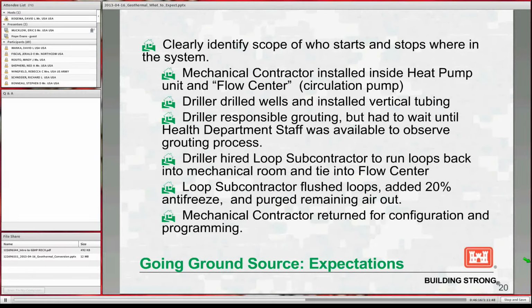The loop subcontractor also has this cart thing that they hook up and flush the tubing out to get any debris out and get all the air out, as well as adding a 20% antifreeze solution. In my case, I had to come back and do that twice, in two steps basically. Then after the loop contractor is done, the original mechanical contractor comes back out and does the final configuration and programming.